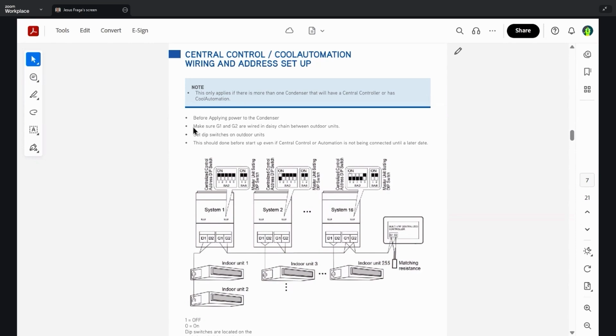A quick note here is to make sure that G1 and G2 are wired and daisy chained between the outdoor units. Set the dip switches on the outdoor units. This should be done before the startup, even if a central control or CoolAutomation is not being connected until a later date. If you try to do this after the fact, you will have addressing conflicts and all sorts of other issues, and the system will give you the error codes pertaining to that fault.